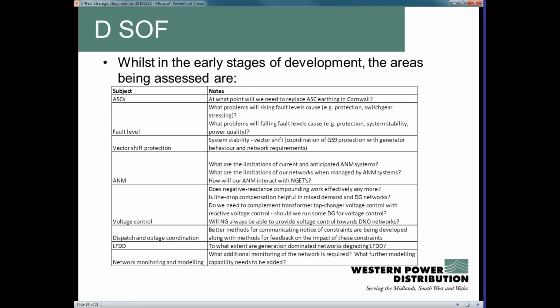The top one is arc suppression coils, or Petersen coils. This is a particular form of earthing system used where ground conditions make earthing more difficult, but it also has the advantage of being able to hold single-phase faults on the network for a period of time before interrupting supplies.